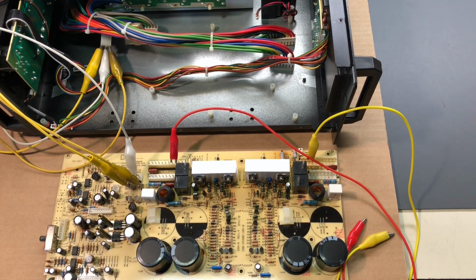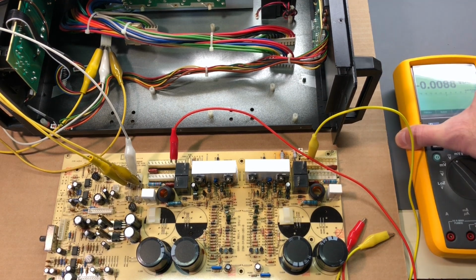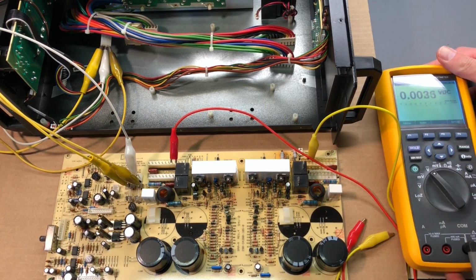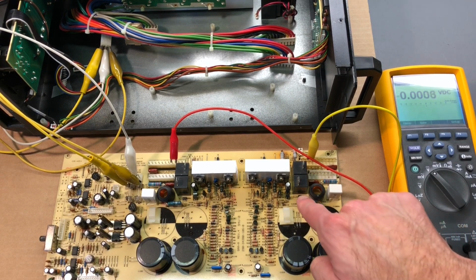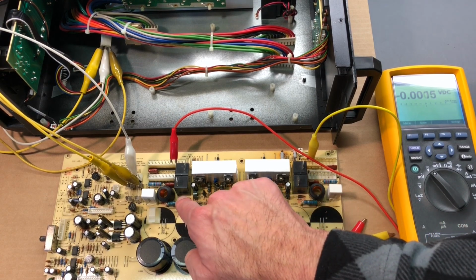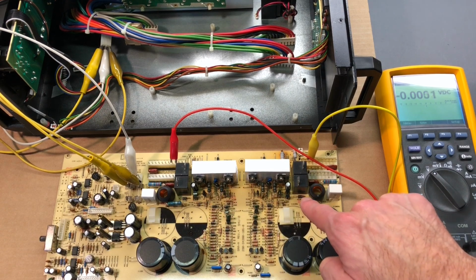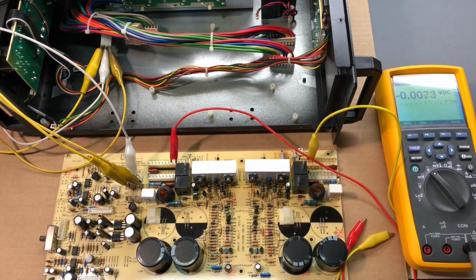I'll grab my digital multimeter here and get this into the shot so you can see the numbers on there. Let's take a voltage reading across the coil. There's a diode right there, and another one next to each relay. Those are the voltage kickback suppression diodes, so when the relays switch off, they suppress the kickback voltage generated across the coil.